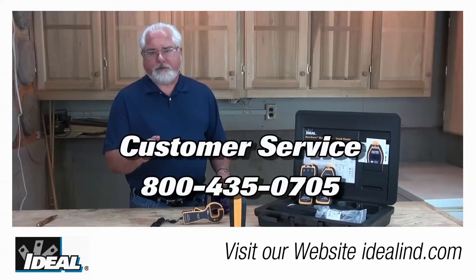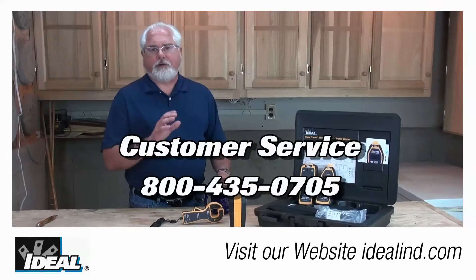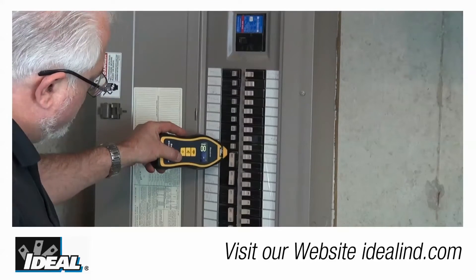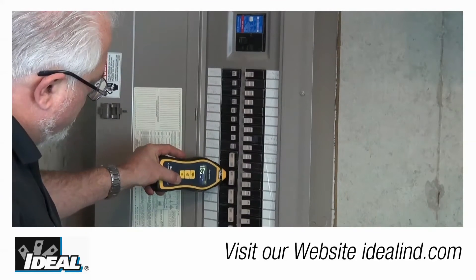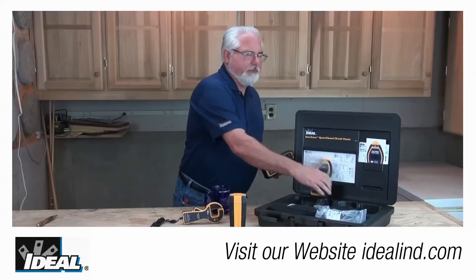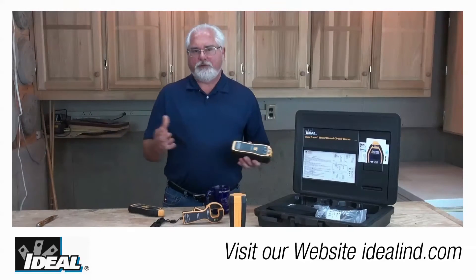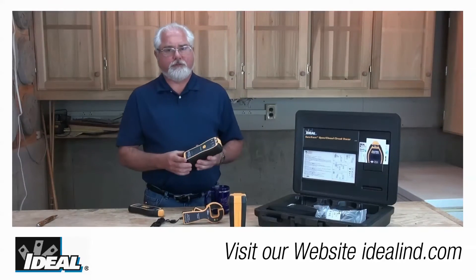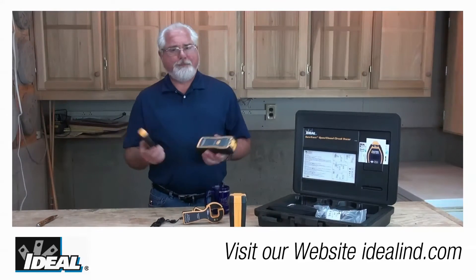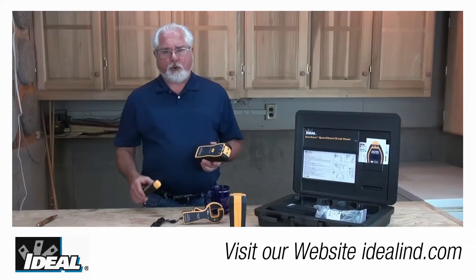If you'd like to learn more about these circuit tracers, you can find them on our website and find out how you can purchase one. Tracing wire effectively throughout a building and finding a breaker or fuse back in a panel is all about generating a very strong broadcast signal you can put on a conductor that you can find using a receiving unit. By generating a very strong broadcast signal using the proper techniques outlined in the instruction manual, and having a very sensitive receiving unit, pinpointing a conductor's location or path is a lot quicker and a lot more accurate.